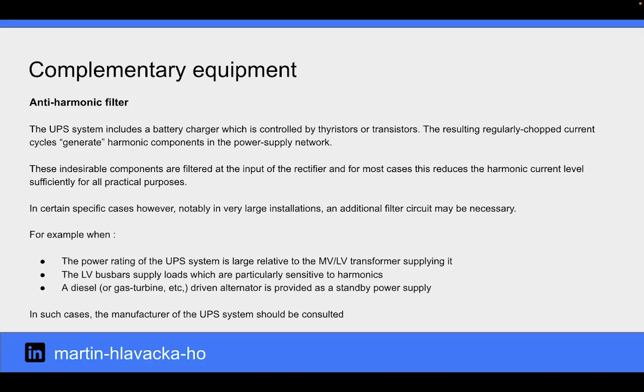The UPS system includes a battery charger that is controlled by thyristors or transistors. The resulting regularly chopped current cycles generate harmonic components in the power supply network. These undesirable components are filtered at the input of the rectifier and for most cases, this reduces the harmonic current level sufficiently for all practical purposes. In certain specific cases, however, notably in very large installations, an additional filter circuit may be necessary.